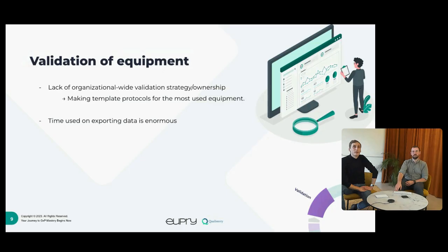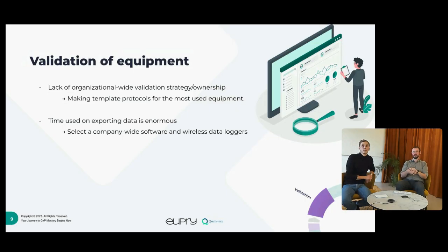Another pitfall we see is that the time used on exporting data from validation of equipment can take rather long, and luckily there's a real simple solution to that: we would often encourage companies to use a wireless system that has company-wide software related to it, but most important, that it's a wireless system. Real-time data really is one of the key improvements one can make in optimizing the whole validation process.